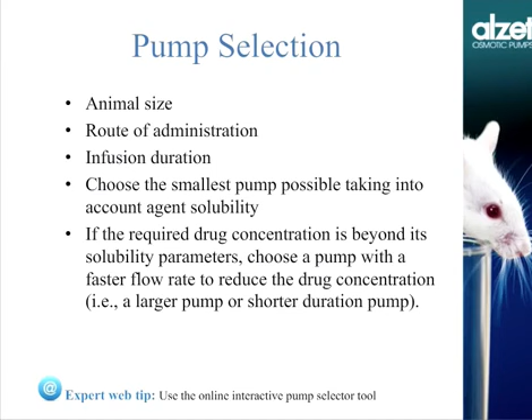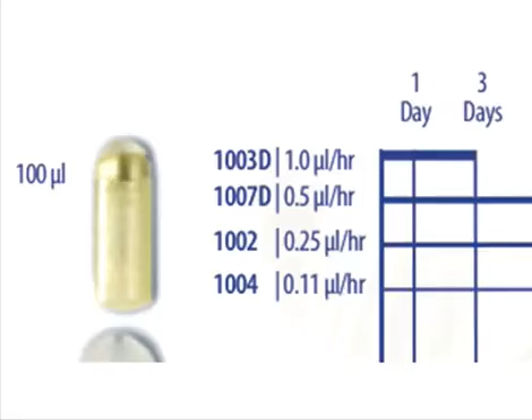Going back to our table of pumps, let's go through an example together on choosing the best pump. Let's say, for example, you wanted to infuse your solution for 14 days continuously. Again, we recommend considering the smallest pump possible for a given duration. In this example, the smallest 14-day pump is model 1002. Again, the 100 means 100 microliter volume, the 2 means 2 weeks. You'll see here that this pump infuses at 0.25 microliters per hour. Once you crunch the numbers, if you find that the required concentration of the pump, assuming 0.25 microliters per hour, is beyond the solubility parameters of your drug, then you'll need to consider a faster infusing 2-week pump. In this case, one example would be model 2002.